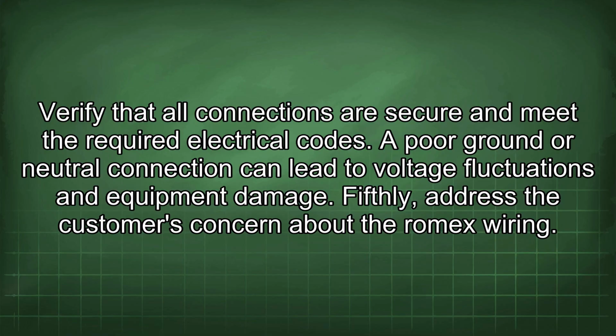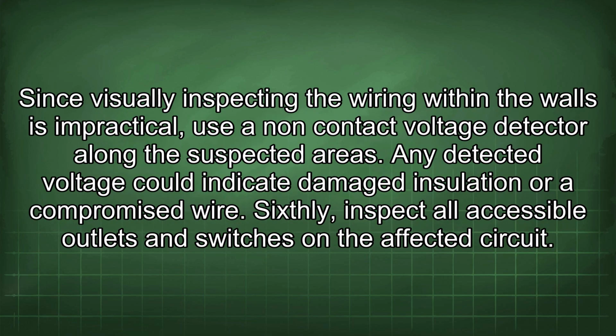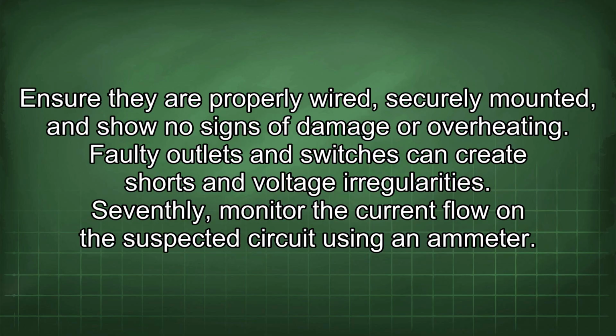Fifthly, address the customer's concern about the Romex wiring. Since visually inspecting the wiring within the walls is impractical, use a non-contact voltage detector along the suspected areas. Any detected voltage could indicate damaged insulation or a compromised wire. Sixthly, inspect all accessible outlets and switches on the affected circuit. Ensure they are properly wired, securely mounted, and show no signs of damage or overheating. Faulty outlets and switches can create shorts and voltage irregularities.